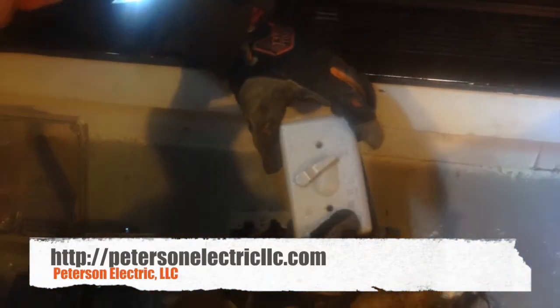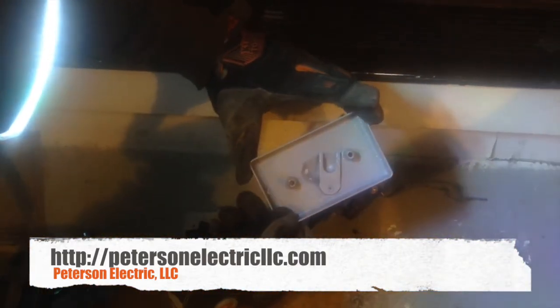I don't really think personally these covers are 3R-rated well — I wouldn't use these for switches and disconnects in my opinion. I think it rusted because the water sat there, and I still wouldn't trust it because I had water up and down the whole thing inside.